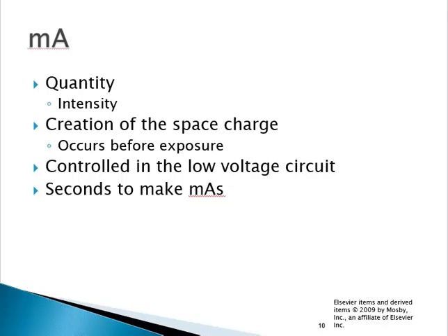In the last recording I talked about KVP. Now we're going to talk about MA, time, and MAS. MA directly controls the quantity of electrons that we accumulate on the filament and eventually send across the tube to interact with the anode.